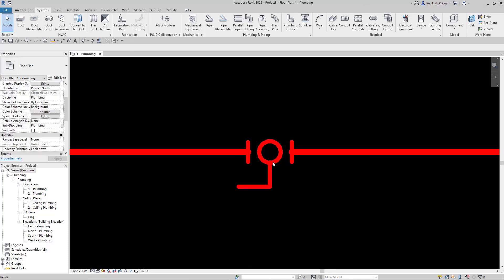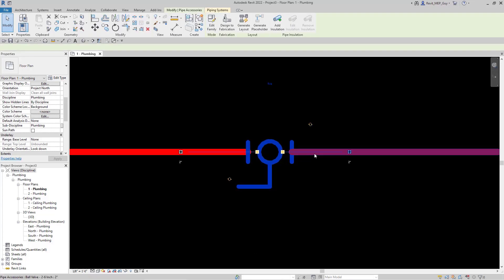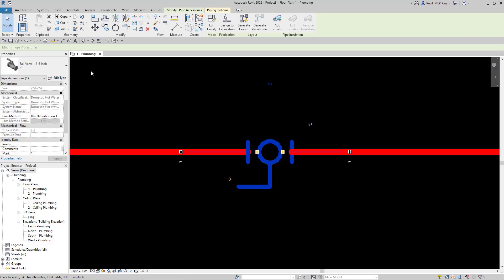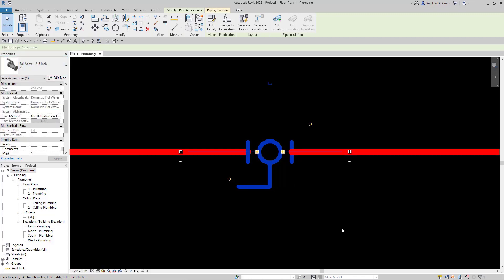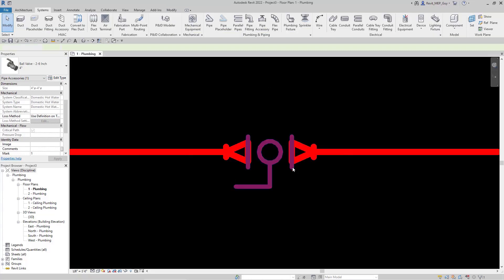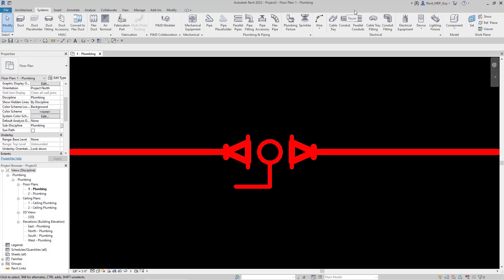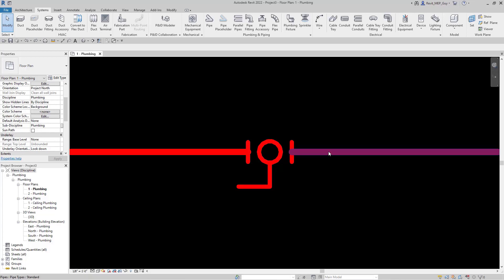It's important to remember that the size of this valve dictates those increaser symbols and whether they're going to show up or not. For instance, if I change this to a four inch ball valve, I'm going to get more increaser symbols because my pipe's not the correct size. So that's something to keep in mind when working with ball valves or any piping accessory in Revit. Let's undo that by hitting Control Z, and now I'm going to change my pipe size to half inch, because that's a typical size we work with.